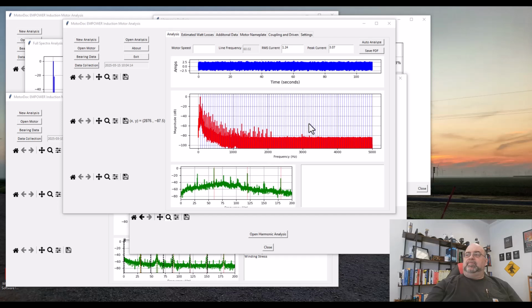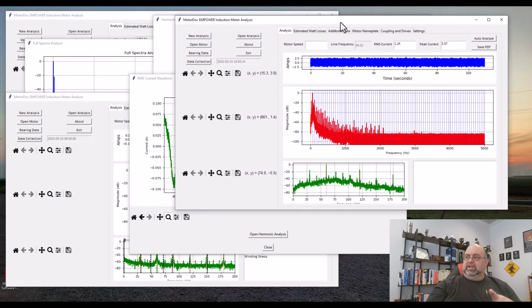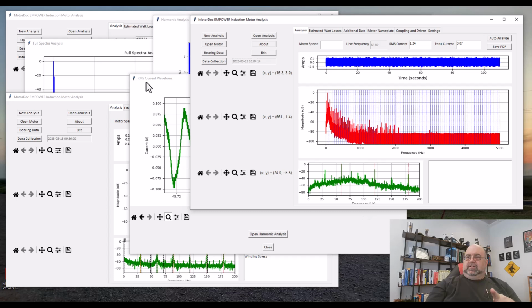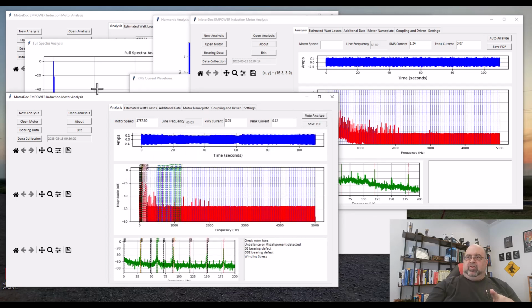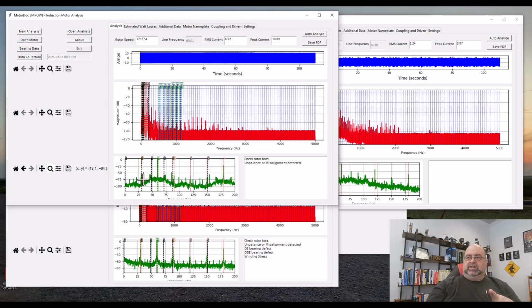So we'll know in the next test, because I switched everything off and did an extra test, and I'm going to keep this rolling to show you what that is. Just to put this into perspective, here's what it looked like with the current clamp, and here's our direct measurement, the true measurement of what's going on in the magnetic field of the machine. This is a much higher current, so it's drowning everything else out.